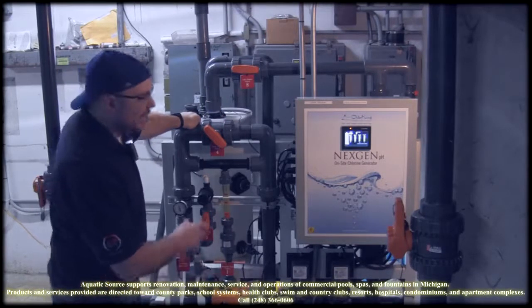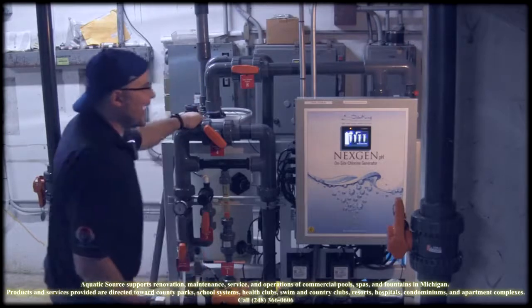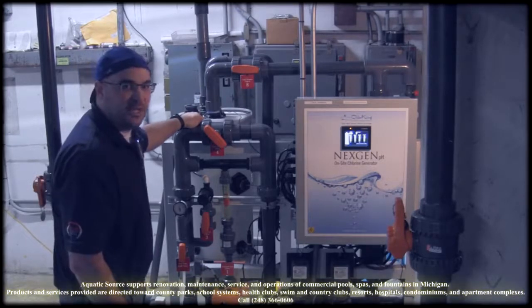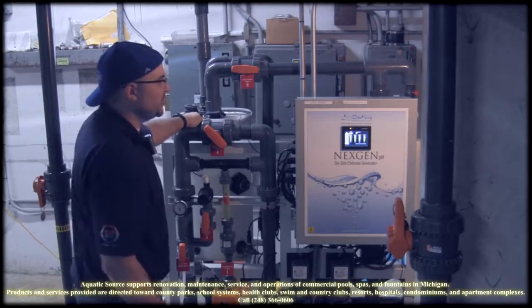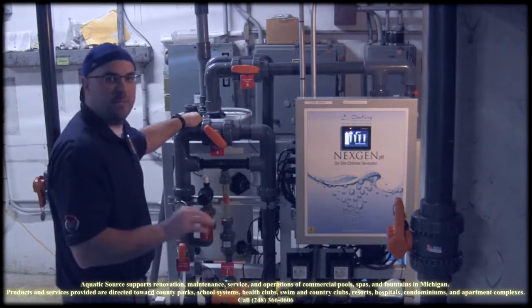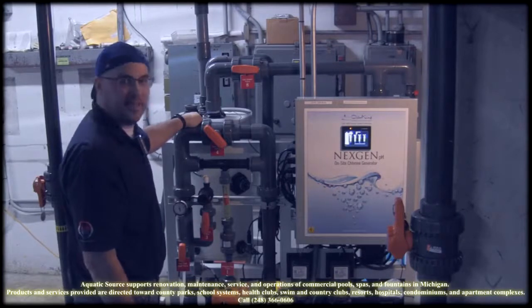This system will make the equivalent of 20 gallons of 12% liquid bleach in a 24-hour period, which for most high school competition pools in southeast Michigan is a really, really good balance. 20 gallons of chlorine is a lot of bleach.